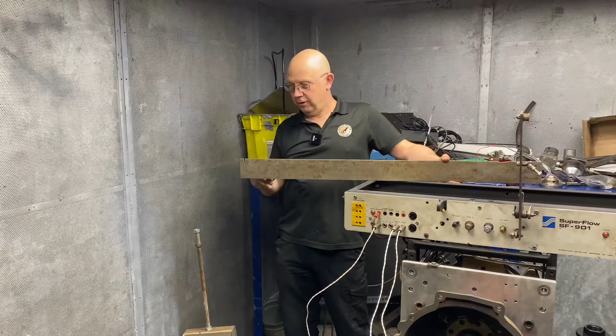If that's all good, what you then do is hang weight on here to simulate the kind of torque that you expect your engine to produce. This will handle anything from 30 pound-foot of torque to 1,000. Obviously you want to calibrate it within the region of what you're doing. If you're testing engines that are making 900 pound-foot of torque, you don't calibrate it with only 17 pound.